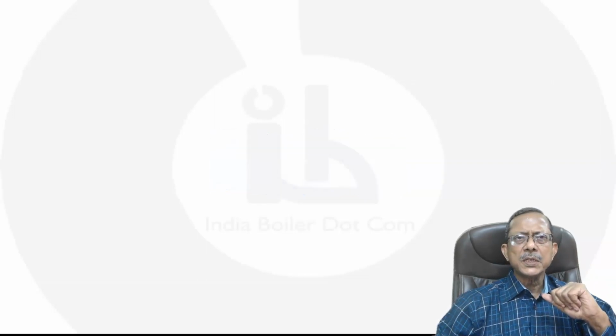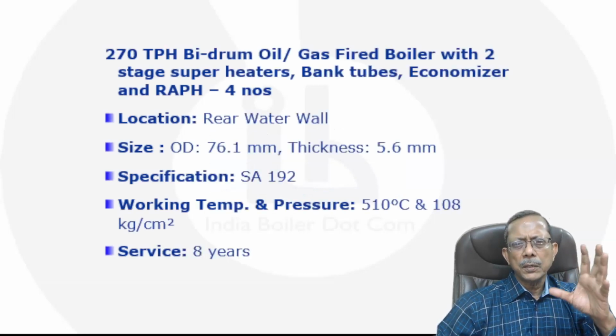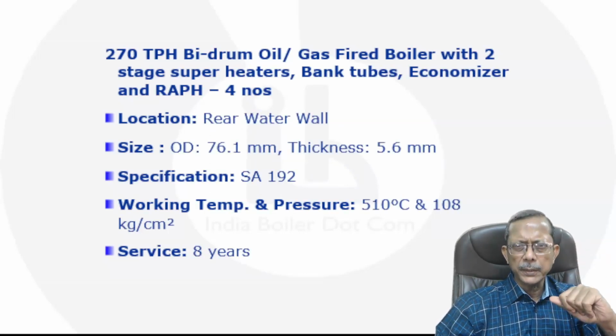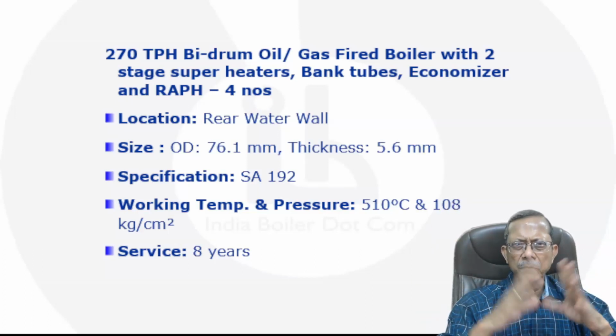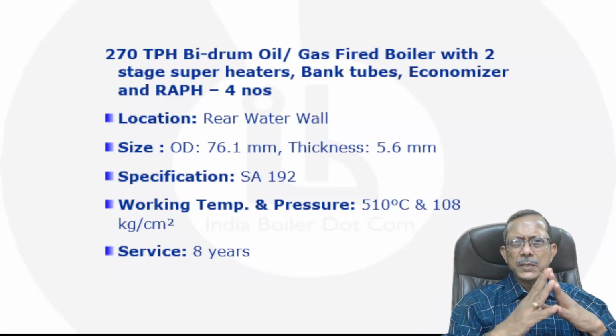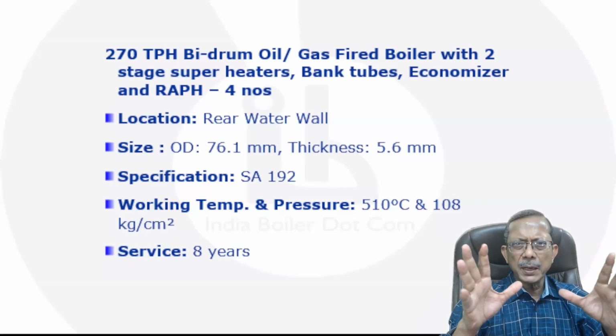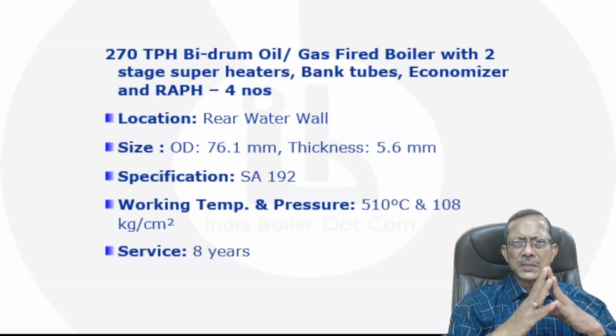So this is a case study on a bi-drum utility boiler. You understand bi-drum: it has a steam drum and a mud drum with a bank tube, 3-pass boiler. It was a 270 tons per hour design capacity boiler.